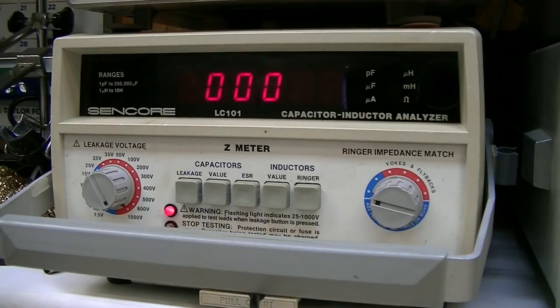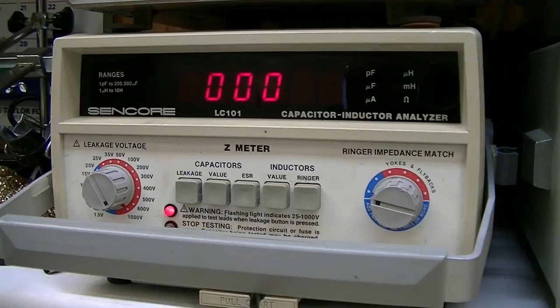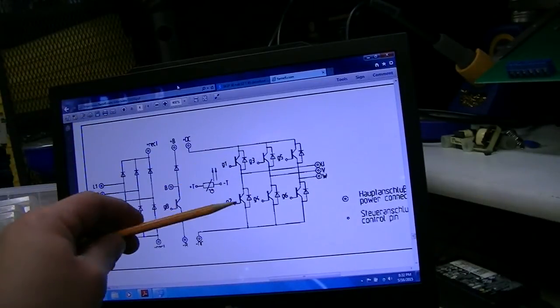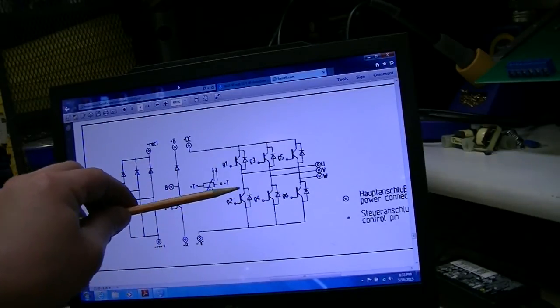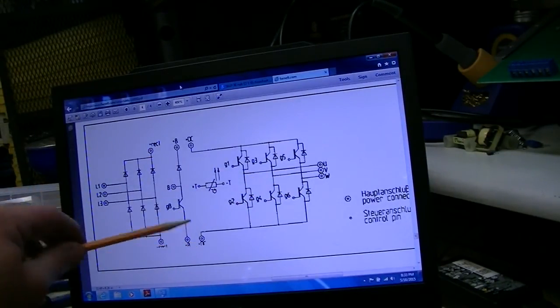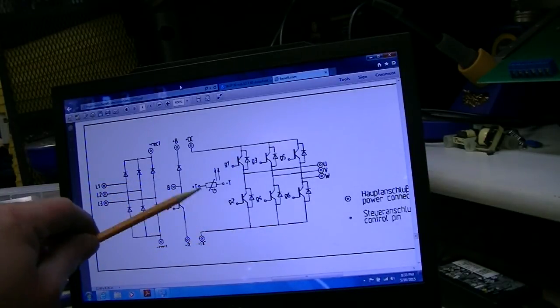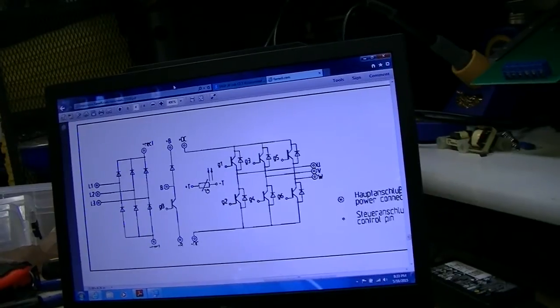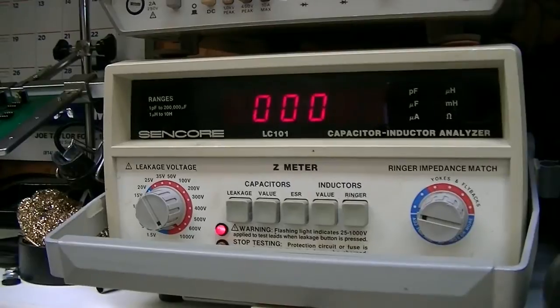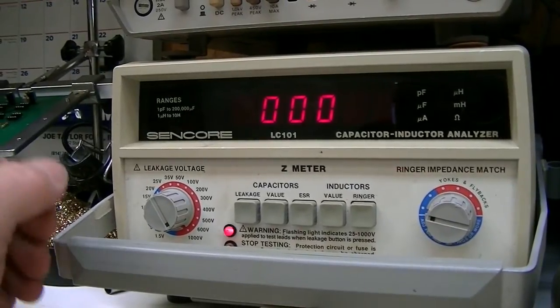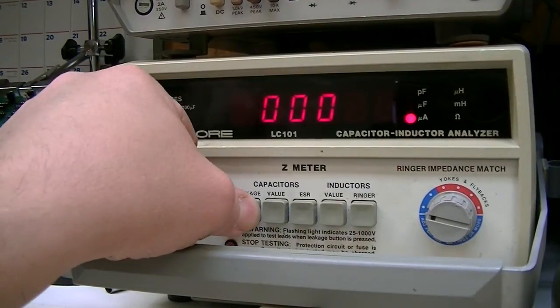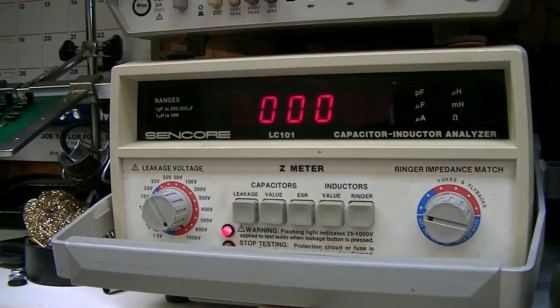Now, I should be able to swap around and go to DC minus, and I think I'll have to swap my polarities around. Let me shut this off, I'll experiment here. Okay, so now I'm checking these lower IGBTs here. The U, V, W, and then also the DC minus is at the emitter. So, we'll see what we've got there. Okay, so there's the U, the V.